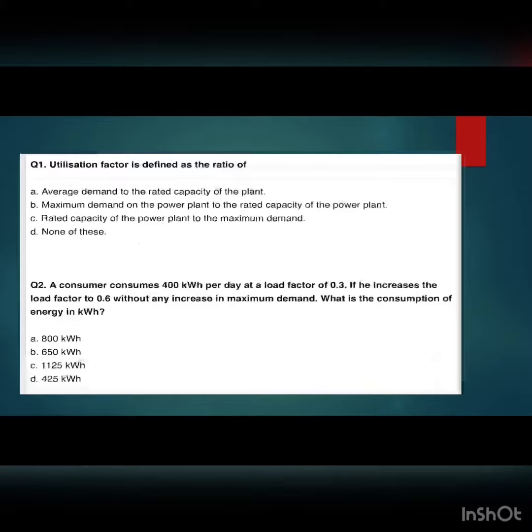Here it says a consumer consumes 400 kWh per day with a load factor of 0.3. The load factor is increased to 0.6 but maximum demand is not increased - it remains the same. The load factor is average upon maximum demand, which is average energy consumed per day upon maximum demand. So our average energy is 400.